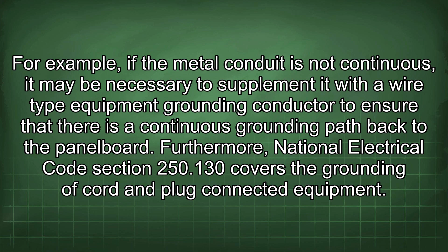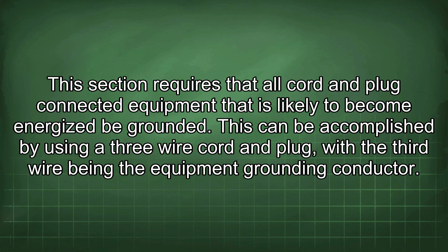Furthermore, National Electrical Code Section 250.130 covers the grounding of cord and plug connected equipment. This section requires that all cord and plug connected equipment that is likely to become energized be grounded. This can be accomplished by using a 3-wire cord and plug, with the third wire being the equipment grounding conductor. The equipment grounding conductor must be connected to the grounding pin on the plug, and the grounding pin must be connected to the grounding terminal on the receptacle.